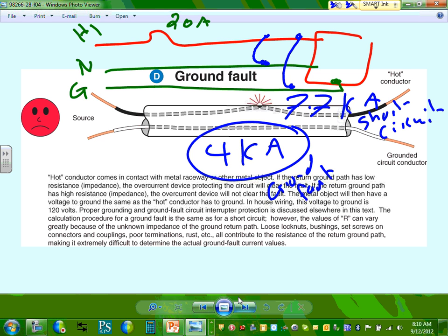Of course we can. When it comes to the short circuit, the term that they use is K, kilo. You don't say 10,000 amp. That's only the naive new in the industry that say 10,000 amps, right? The term that they use is 10 kiloamp when it comes to the short circuit. When it comes to the rating of the circuit breakers, we can say 100 amp. 100 amp is the rating of the circuit breaker: how much you can pull continuously out of this circuit breaker in normal condition. Any questions, guys, about the ground fault condition for the circuit? Very, very important. Cool? All right, so let's go to the last one.